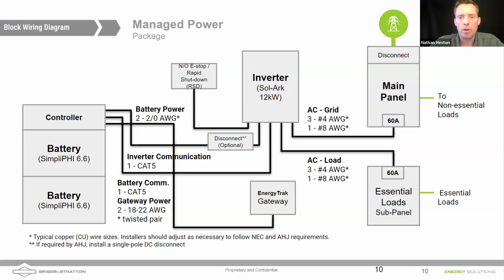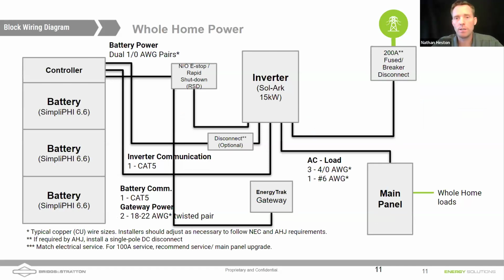And the wiring diagram would look essentially like this, where you see that main panel, but you also have an essential loads panel on the right side. We are able to pass through, I believe it's 63 amps through that Sol-Ark 12K. And so you could have all of your power coming from that main panel, just powering the essential loads panel until there's a grid down situation. Or you could integrate solar through that inverter and have solar contributing and even charging the batteries and powering the essential loads or feeding back to grid.